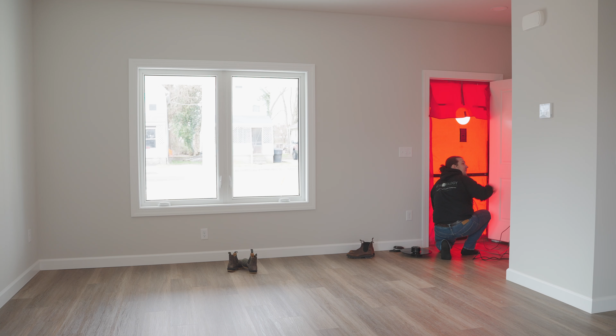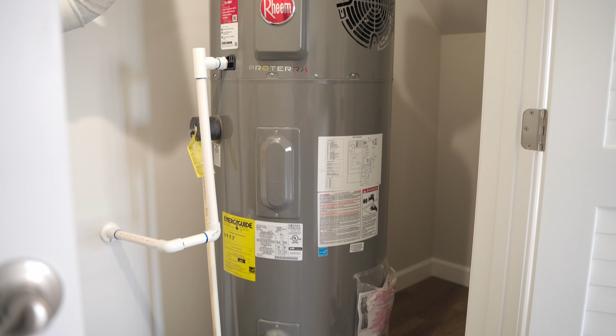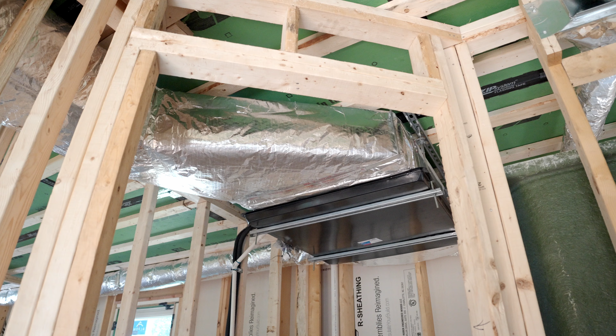We always do midpoint testing to identify any of those trouble areas, because there's nothing worse than trying to chase air leaks that are behind insulation and drywall and in a finished space. You just don't have the ability to make that building as tight as you do when it's wide open at the end of the rough-in stage.